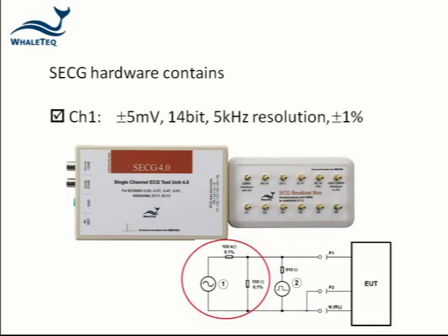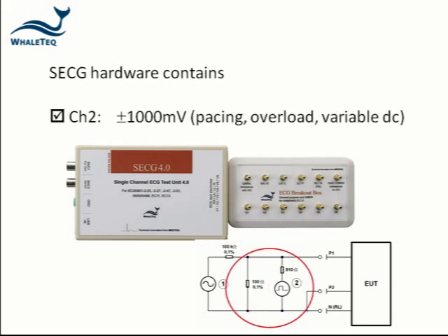A low level channel with up to plus or minus 5 millivolts with 14-bit 5 kilohertz resolution and 1% accuracy, and a high level channel for pacing, overload, and variable DC offset of up to plus or minus 1000 millivolts.